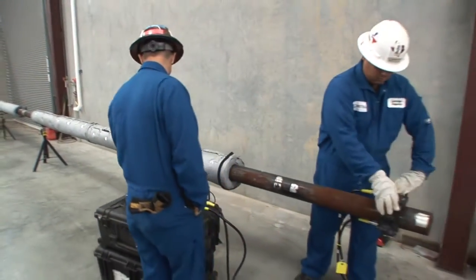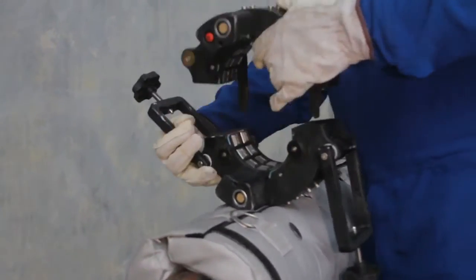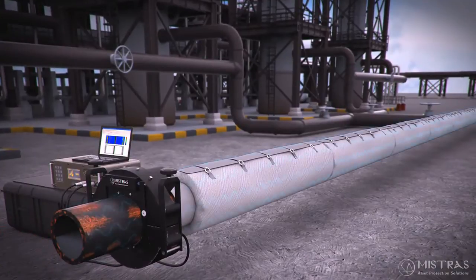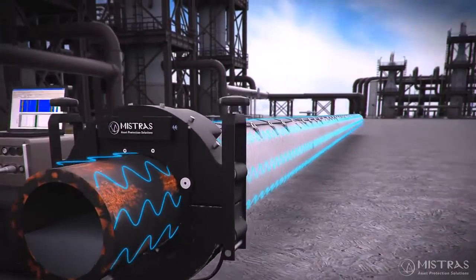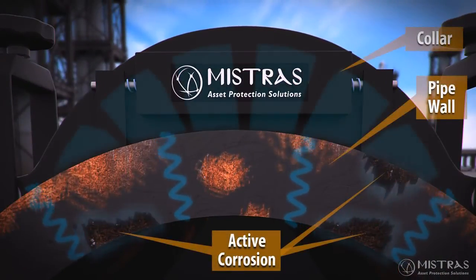Mistras utilizes long-range ultrasonics for the rapid scanning of a large volume of piping to detect areas of metal loss. These areas are detected by using a ring of transducers and a collar placed around the pipe. These computer-controlled transducers emit low-frequency ultrasonic sound waves transmitted bi-directionally from the source. These low-frequency ultrasonic waves travel through the pipe, where damage such as corrosion and erosion is detected and recorded.